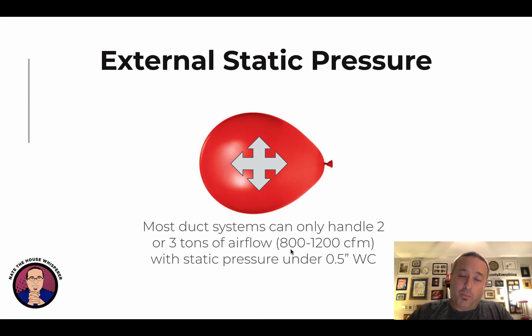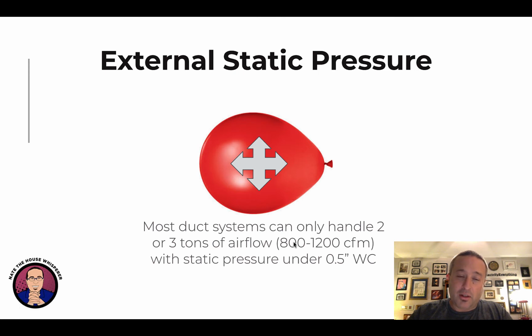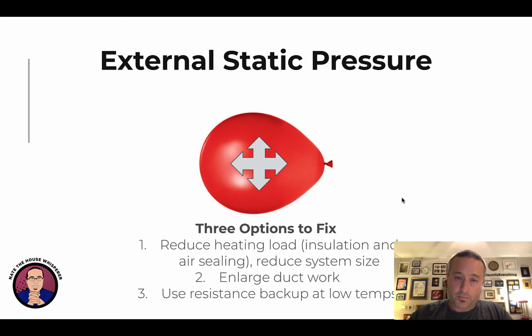Every ton of airflow is 400 cubic feet per minute, give or take. It can be as low as 275, but that gets into a whole other thing. Like that'll make your air conditioner suck all kinds of moisture out of the air because the coil gets really cold, but that's beyond the scope of what we're talking about here. But in general, if you think 400 CFM per ton, that is kind of the standard. So 2 tons is 800, 3 tons is 1,200 CFM. And very few systems as they stand can handle more than 1,200 and stay under 1/2 inch of water column. So you have to be careful with that sort of thing.